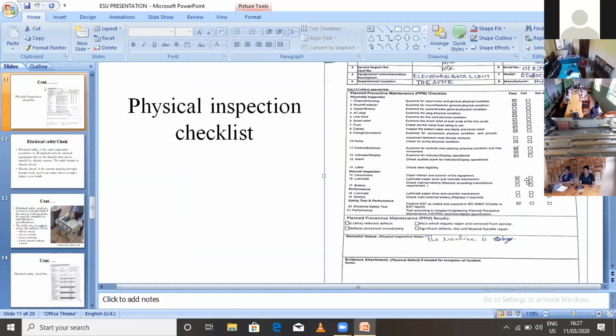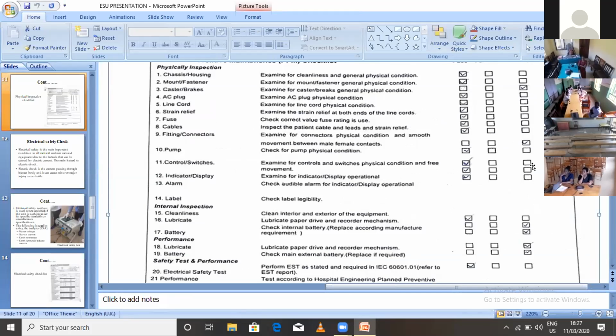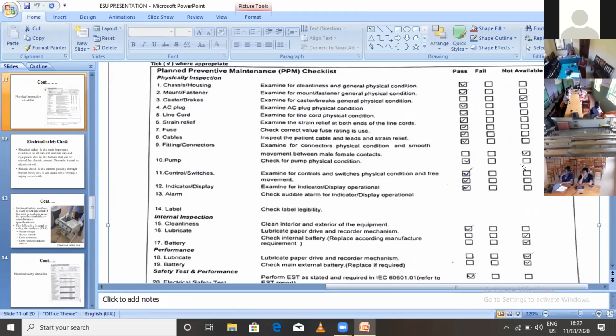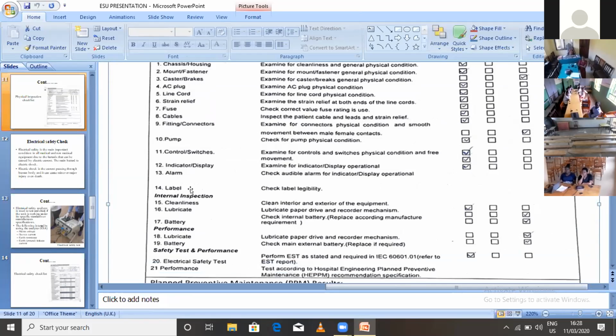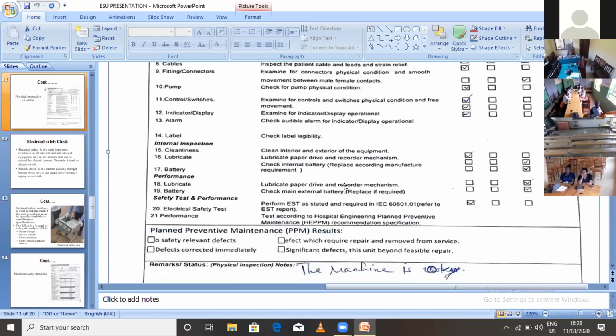So now you can see, as from above, we have so many things to judge during our maintenance. For physical inspection there is chassis and housing, mount and fastener, casters and brakes, AC plug, line cord, strain relief, fuse, cables, fittings and connectors, pumps, controls or switches, indicators, display, alarms, label, and battery. All these are used to check during physical inspection, but they vary according to the equipment.